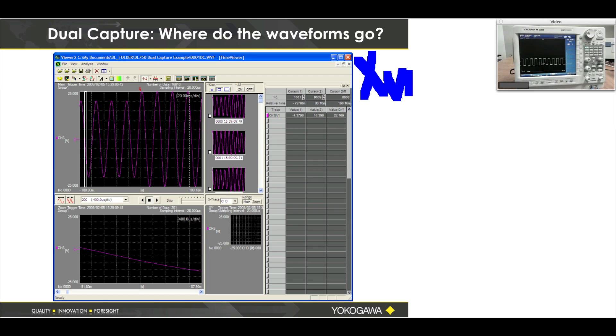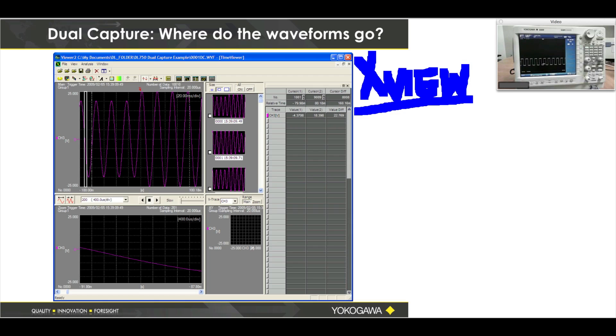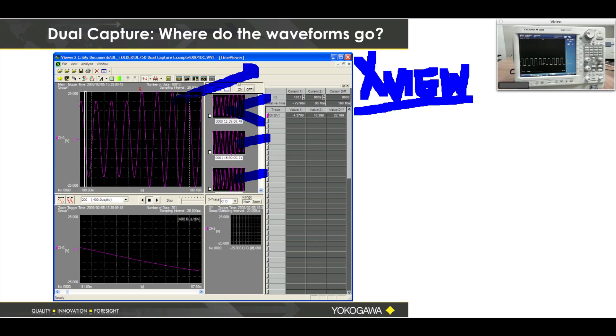Where do the waveforms go? This is X-Viewer, the software I told you about earlier. If you do not have it, please let me send you a free copy — it runs in trial mode and you have a permanent license to trial mode. You can put it on any computer and it will always let you see your waveforms. In the main screen of X-Viewer I have the main acquisition, and then for each event — each surge — I have another window I can click on and look at it in the big window and zoom on it.